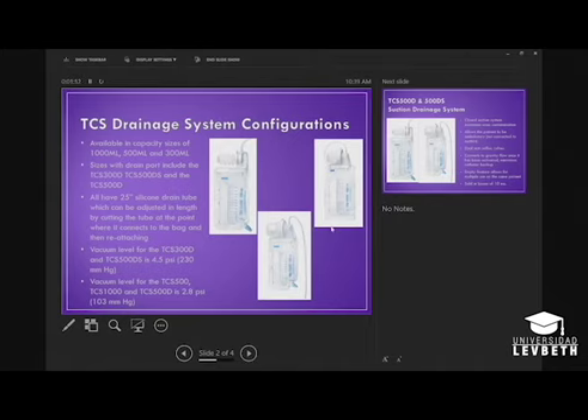They come with a clip so they can clip the bag on the patient's gown, so it doesn't pull the catheter out when they get up. The PSI levels range from 2.8 to 4.5. So the DS has more PSI than the larger ones, which is 2.8. They'll attach the catheter, then take this bag and luer lock it directly to the catheter, squeeze the top bellow once, which activates the suction, and squeeze the bellow again, it'll fill up with fluid, you squeeze it again, and it shoots the substance down into the bag. If you look at that first image, there's a little piece of white tubing coming from the bellow down into the bag. That is an anti-reflux valve. So once you squeeze it, it won't allow it to go back to the patient's catheter. It goes directly into the bag.